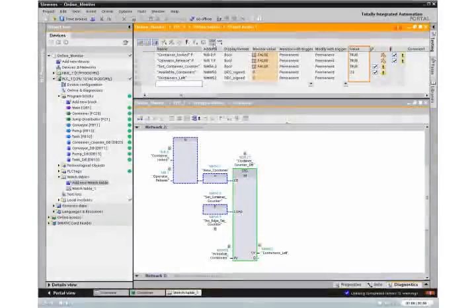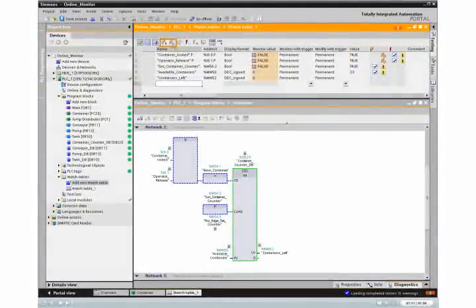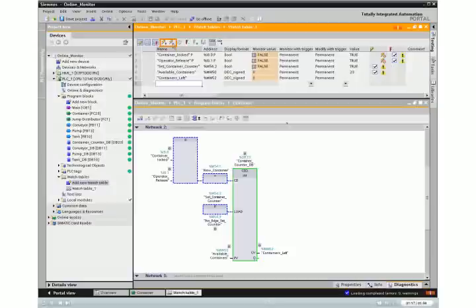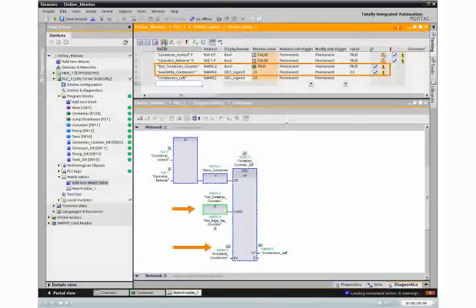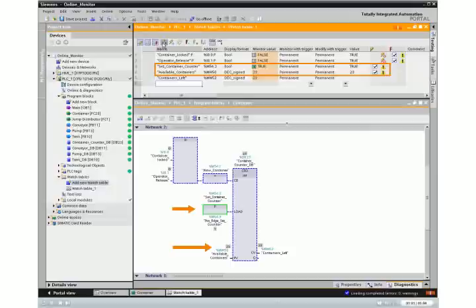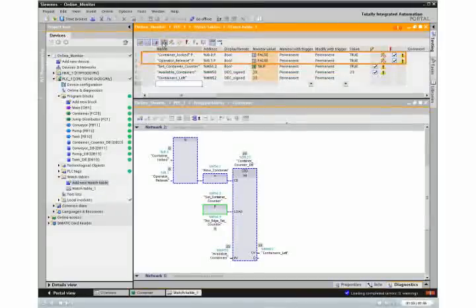You can now pre-assign values to individual variables and run different sequences. By using the buttons for immediate or time-triggered manipulation, you can assign a fixed value permanently to inputs and outputs using the forcing function.